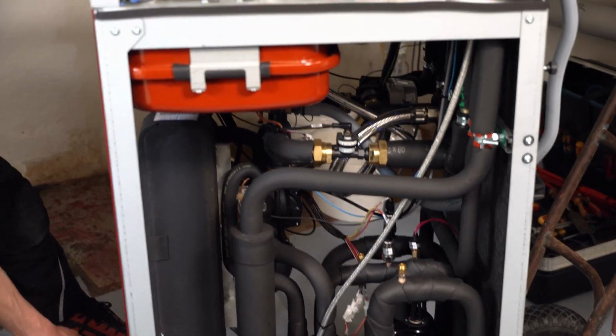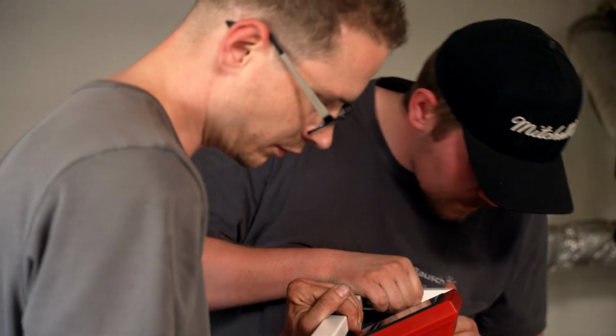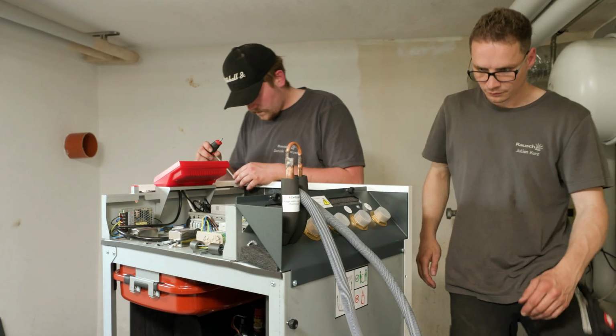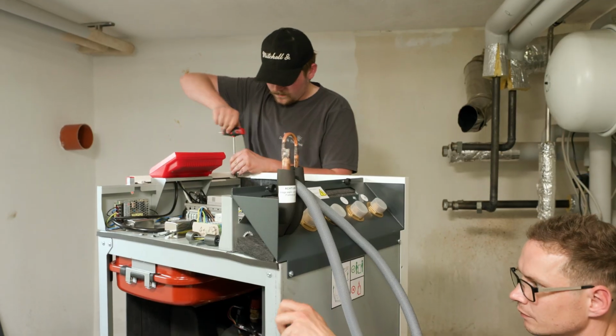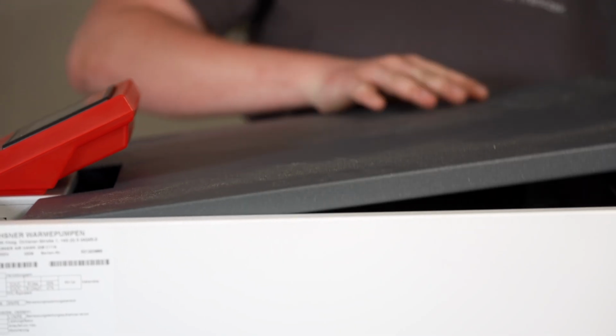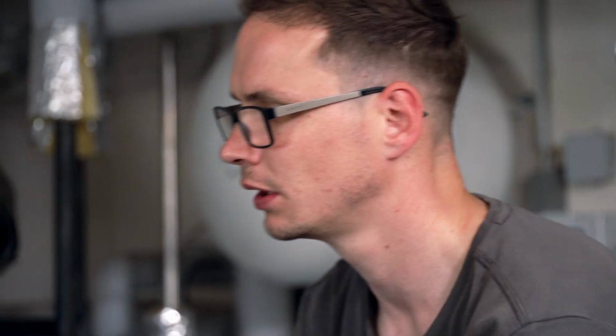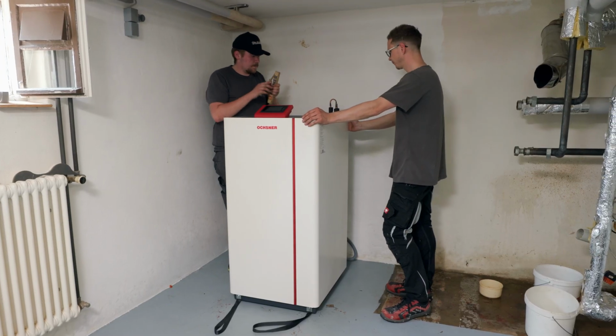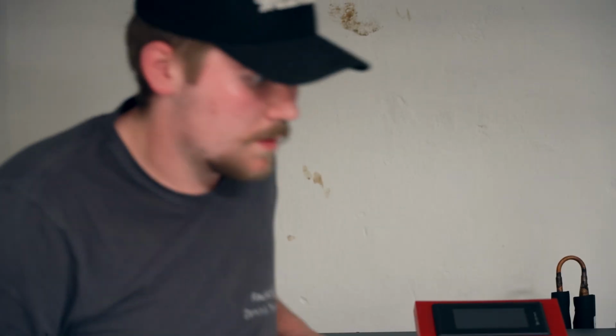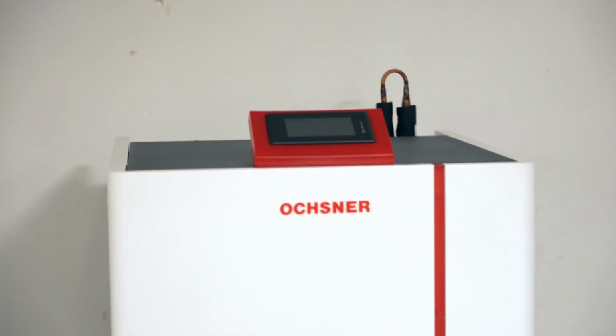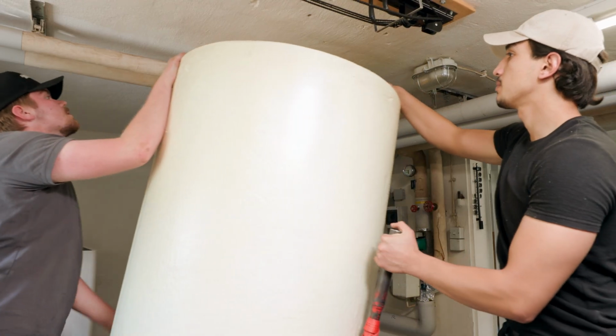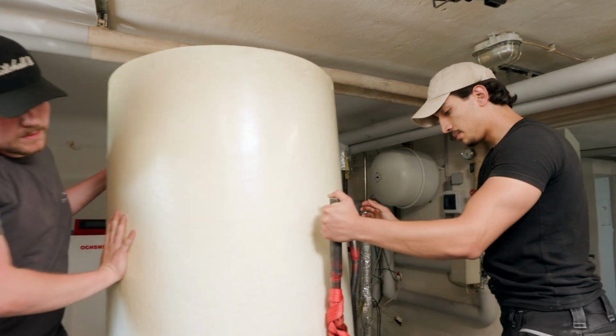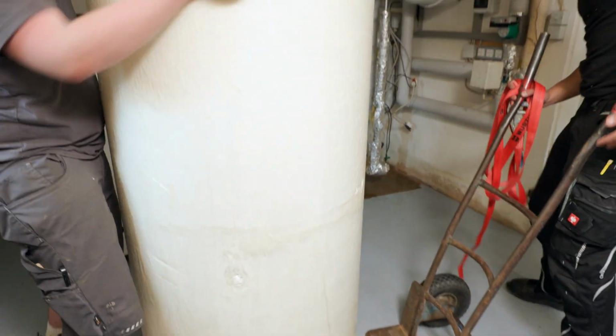In order to keep the electricity costs from becoming too high, the heat pump should generate at least 3 kilowatt hours of heat from 1 kilowatt hour of electricity. The Rommels have an older home, and even there the heat pump generates 3.5 kilowatt hours of heat from 1 kilowatt hour of electrical energy. In addition to the heat pump and the outdoor unit, the entire system also has a buffer tank. The tank can maintain the heat supply for a few hours when the heat pump is not running.